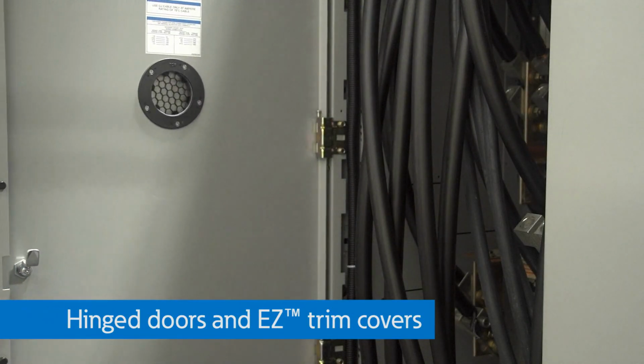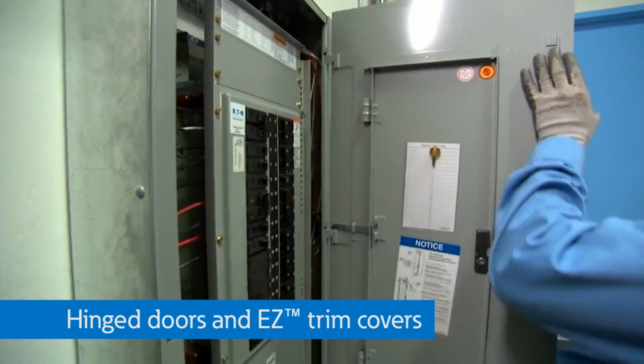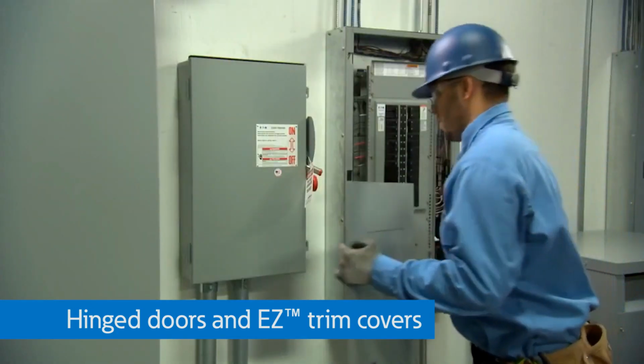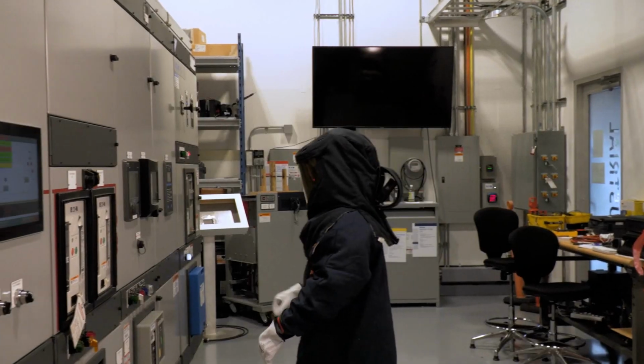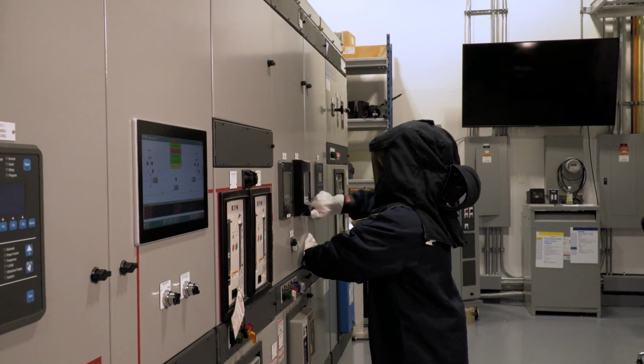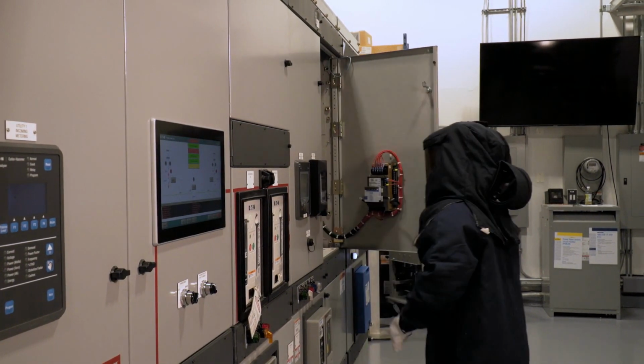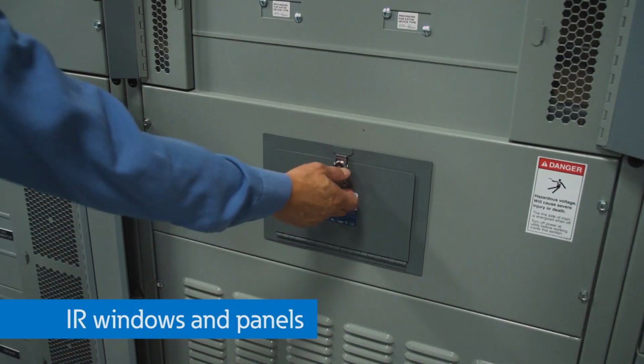Solutions like hinged doors and easy trim covers make for a much safer opening or removal of doors. However, for many years now, opening energized electrical equipment for any reason, including for energized inspections, aside from potentially being a safety hazard, is either prohibited outright by the site owner or prohibited or severely restricted by OSHA, NFPA, or others. These prohibitions exist regardless of workers wearing a 40-calorie suit. In addition, even if it's allowed, it usually requires prohibitively expensive manpower and operational downtime cost to the site owner or operator to do so.